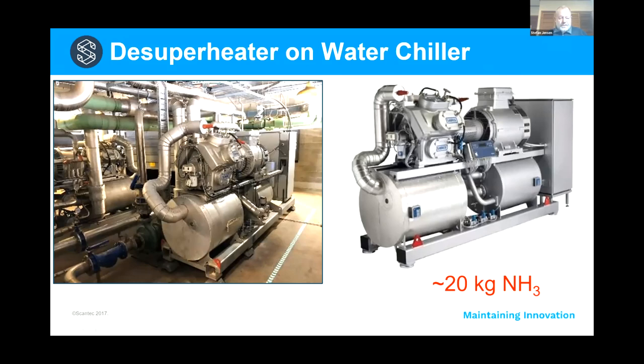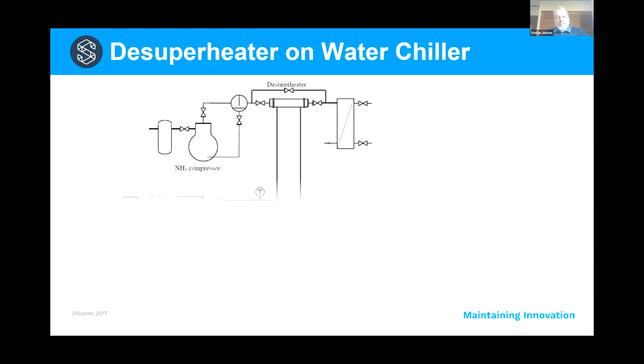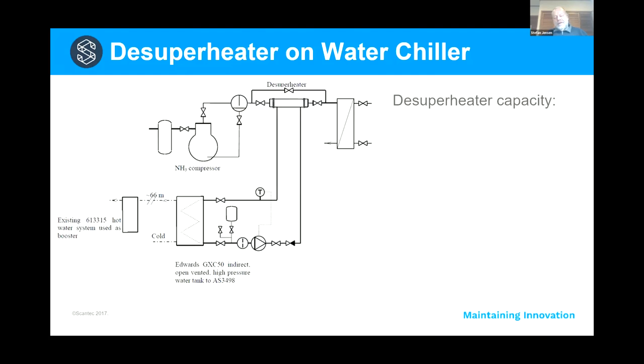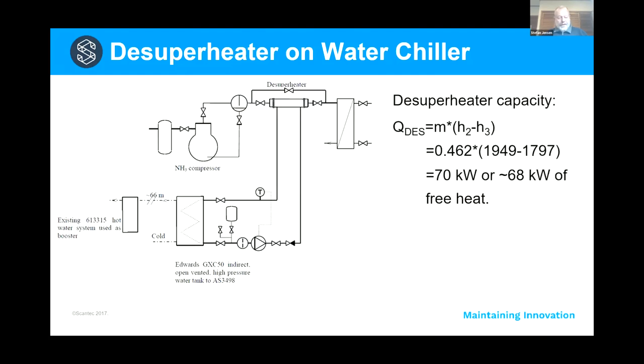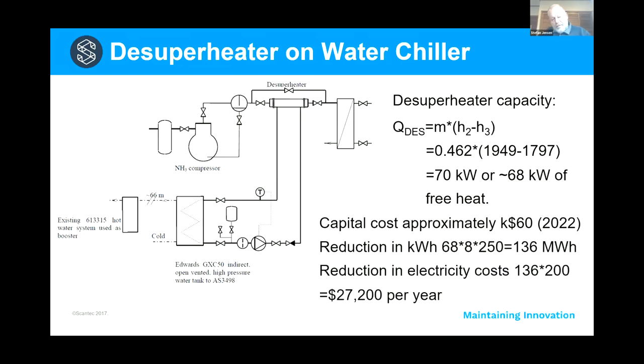I don't know whether you can see my cursor, but it's a little thing about a meter long by about 100 millimeters diameter, sitting right there above the compressor. It desuperheats the discharge gas and produces about 70 kilowatts, which can be used for heating domestic hot water. Now, there's a lot more to a desuperheating system than just the desuperheater and the heat exchanger itself. The heat exchanger, you can see in the top of the picture, is the same rectangle we looked at before.